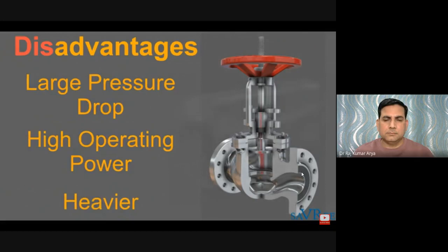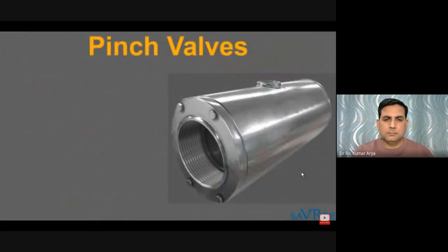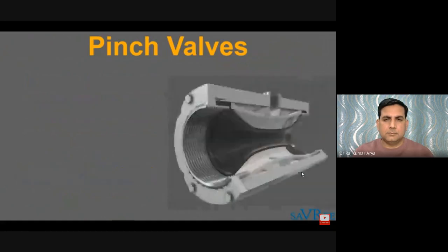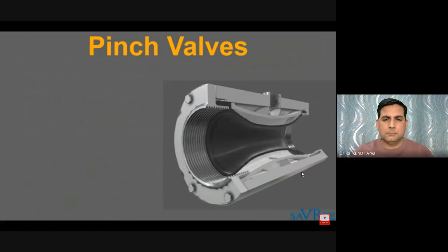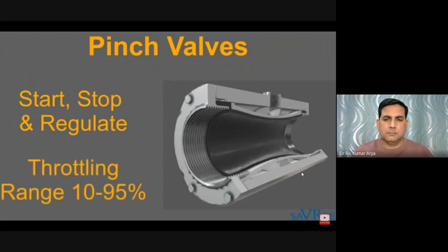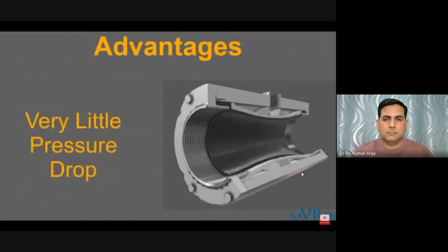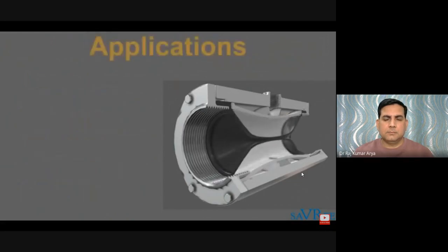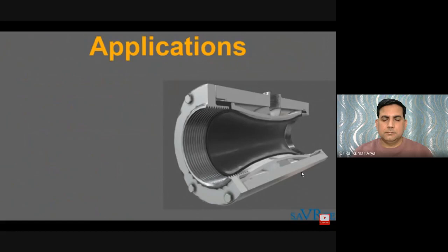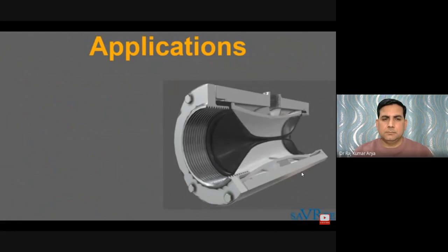Pinch valves are inexpensive and the simplest of any valve design. They consist of a sleeve moulded of rubber or other synthetic material and a pinching mechanism. Pinch valves can start, stop, or regulate flow, with effective throttling typically between 10% and 95% of rated flow capacity. There is almost no pressure drop across a pinch valve. They are ideally suited for handling slurries with large amounts of suspended solids due to their very large seating area, and since operating mechanisms are completely isolated from the flowing medium, they are well suited where corrosion or metal contamination is a concern.